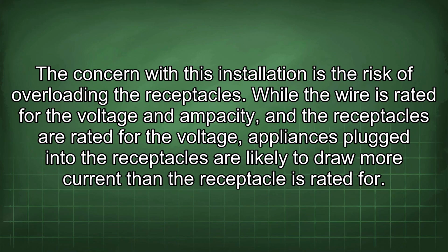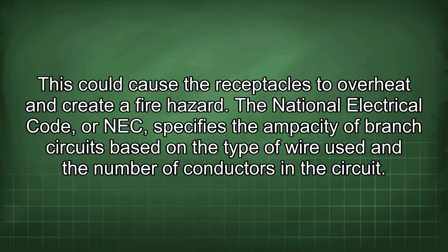Concern with this installation is the risk of overloading the receptacles. While the wire is rated for the voltage and ampacity, and the receptacles are rated for the voltage, appliances plugged into the receptacles are likely to draw more current than the receptacle is rated for. This could cause the receptacles to overheat and create a fire hazard.